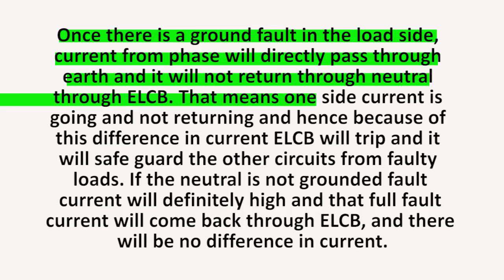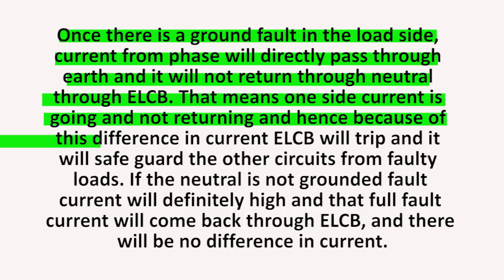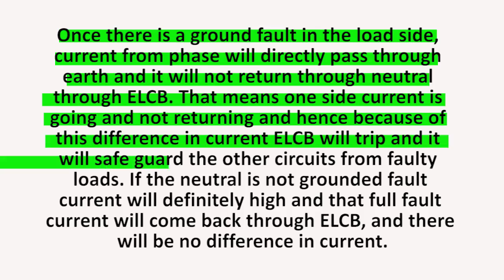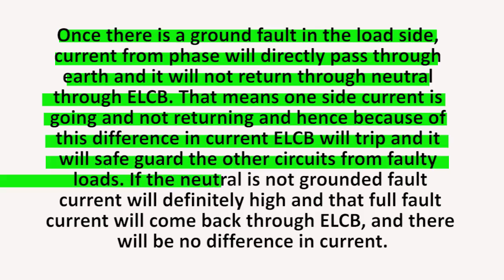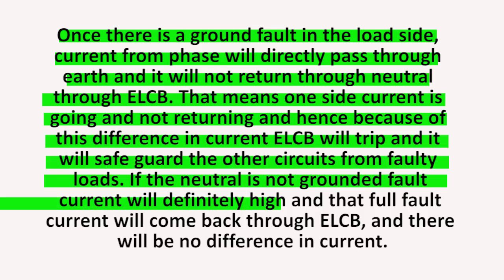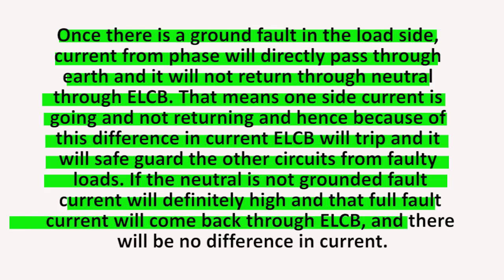That means one side current is going and not returning, and hence because of this difference in current, ELCB will trip and it will safeguard the other circuits from faulty loads. If the neutral is not grounded, fault current will definitely be high and that full fault current will come back through ELCB and there will be no difference in current.